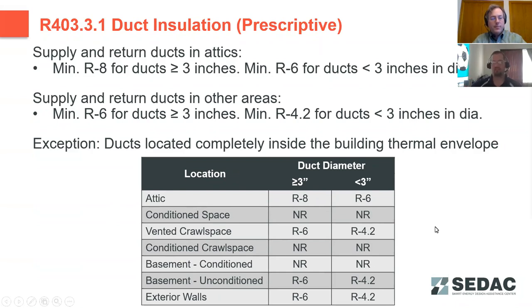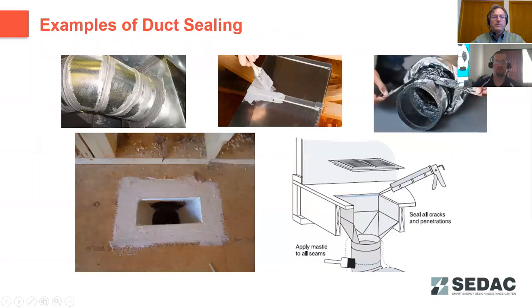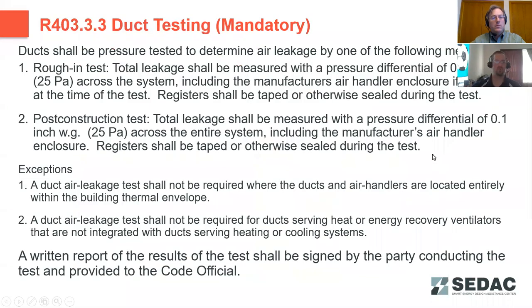The exception to that being, if all your ducts are completely within the thermal envelope of the building, they do not require duct insulation because any heat loss from the duct work or cooling loss from the work is into your conditioned space. So it's still conditioning the inside of the building. All ductwork in residential needs to be sealed. These are some good examples of using mastic, caulking, and UL 181 approved adhesive tape to seal up joints in the ductwork. Also following, especially with flex duct, connecting to hard duct manufacturer installation instructions. Usually they require a zip tie tightened to a certain tension and then covered with a mastic or a tape or something. So duct sealing, very important.